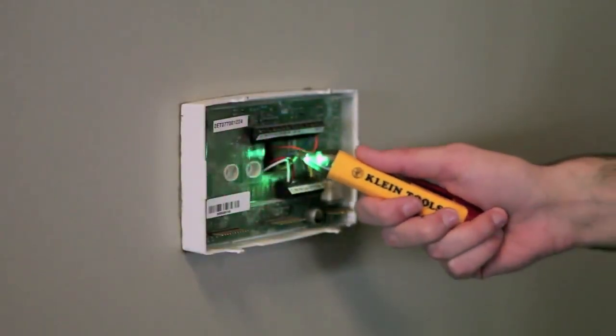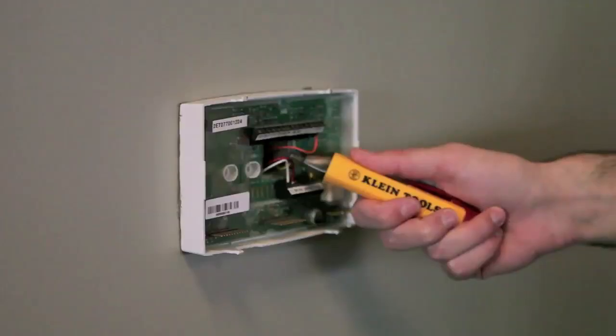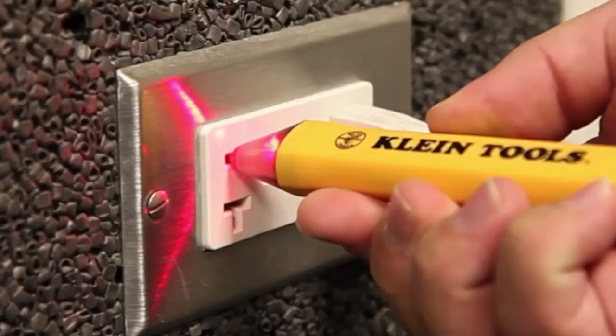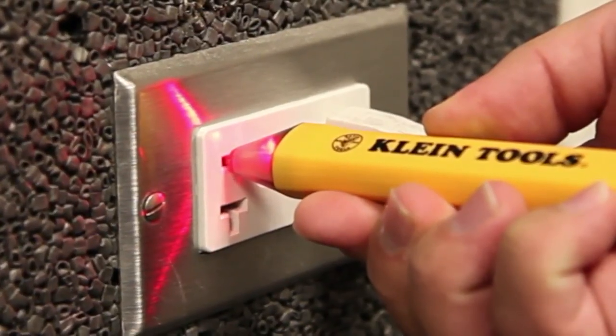The NCVT2 indicates low voltage with a low pitched beeping tone and blinking green LED light. A steady red LED light and low pitched beeping tone indicates the tester is detecting standard voltage.